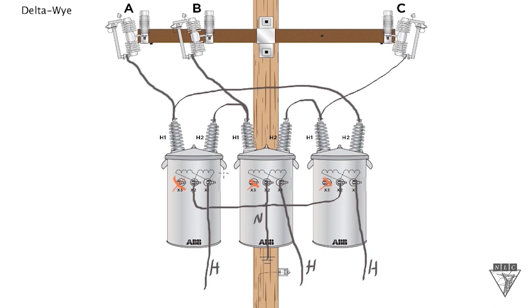So that's the secondary connection on a delta Y connection. X2s are all tied together and then grounded for your neutral, and then coming out of our X1s here, we have one hot leg per transformer.